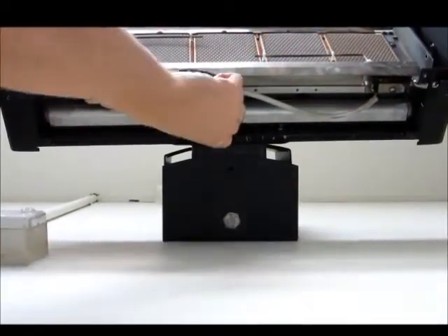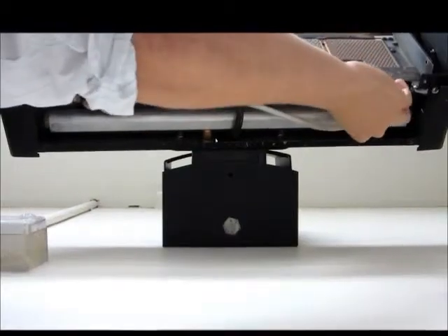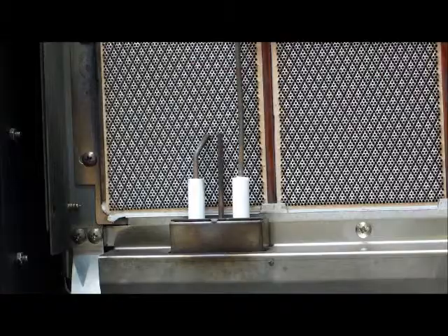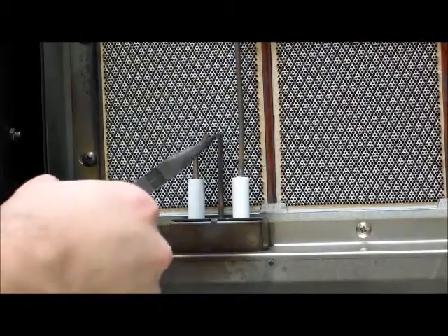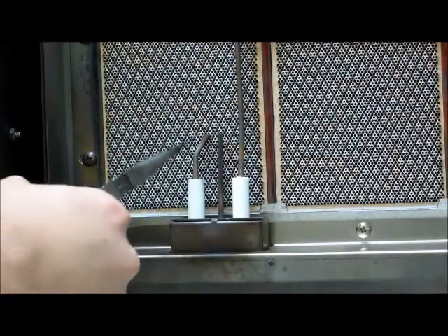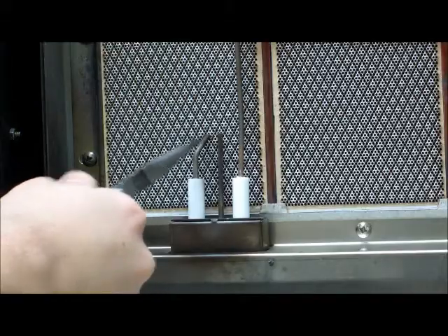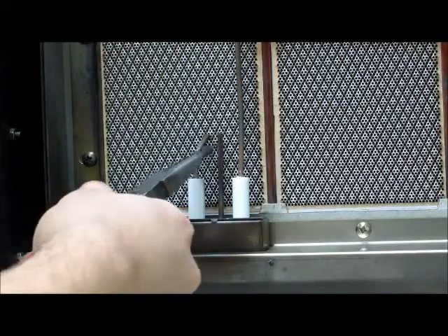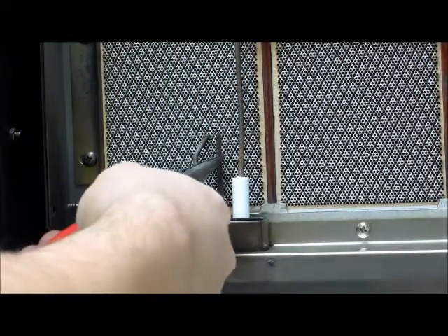If any wiring or connections are damaged, contact your dealer and order a replacement part. Inspect the ignition and earth probes and ensure that there is a 4 to 6 mm gap between the two, as well as between the surface of the tiles and the probes. Adjust accordingly. Any contact between the two will result in a poor or absent spark on the igniter.